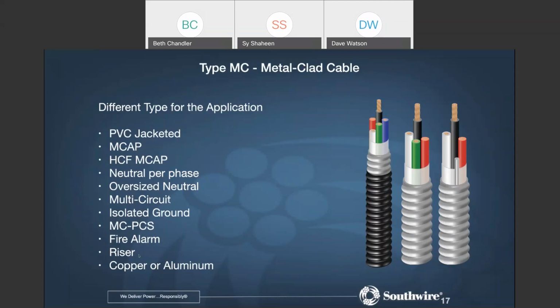Riser MC is constructed such that the conductor support is continuous all the way through the cable. Therefore, you do not have to install the special conduit supports at the prescribed distances vertically. So the chocks that you might have to install for the conductor supports in a junction box are the extra 90s that you would have to install to relieve that weight, that pressure on the conductors. You wouldn't have to do that with the riser MC cable. So you would see a labor and cost savings in the installation of the product.